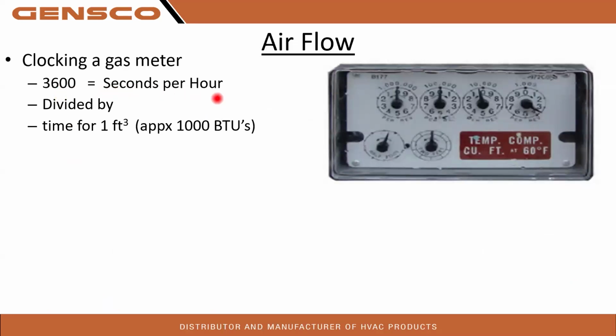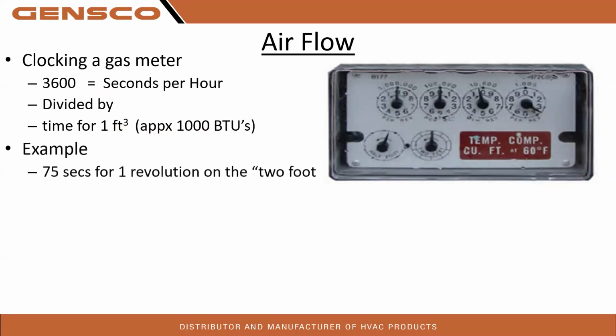You've got 3,600 seconds per hour. Again, make sure that you shut down all gas appliances and you're only running this furnace, right? You're going to be using this 2-foot dial right here. You're going to see it move as your gas is flowing, and just the furnace. Time for 1 cubic foot, approximately 1,000 BTUs. So 75 seconds for 1 revolution. You're going to clock a timer on 1 full revolution, and in this example, it's 75 seconds for that to do one revolution.